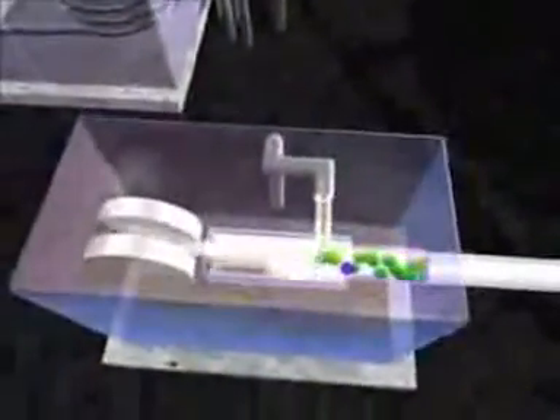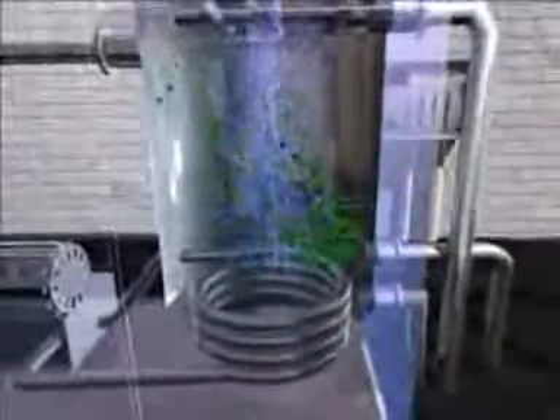The almost unpressurized biogas is then fed into a compressor, where it is brought up to the 70 millibar pressure later required for burning. In order to completely condense any remaining water vapor and to free the biogas from any suspended matter or silicate, the biogas is subjected to a washing and drying process. This is carried out with the vapor at almost freezing point so that the gas is cooled down to a temperature of under 5 degrees centigrade.